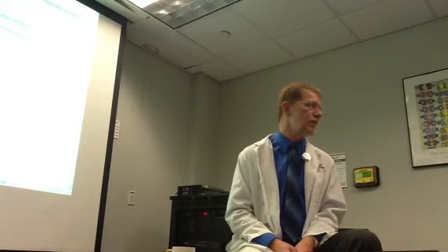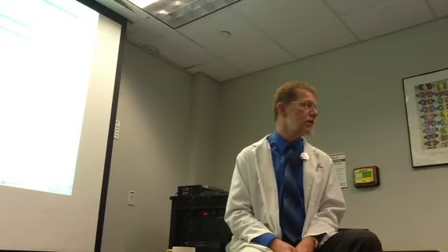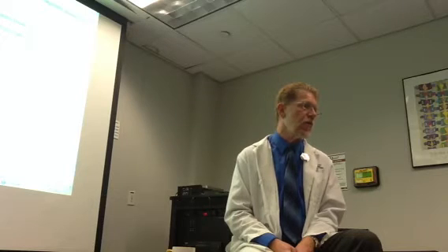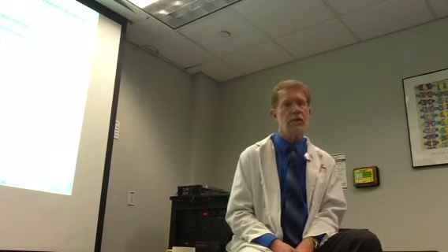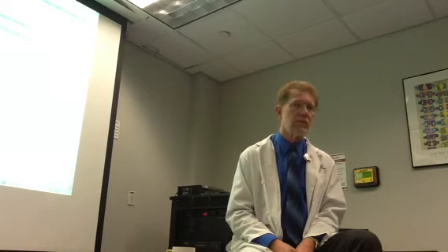Too much noise. Absolutely. Problems with contrast enhancement. Remember that one? Which again, that's actually a 317 lecture. But how you adjust the contrast, you can either mask a hot defect by bringing down the high end of your contrast, or you can mask a cold defect by bringing up the low end. All right? Either way, problem.